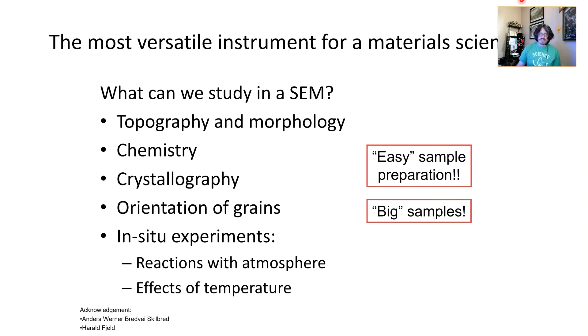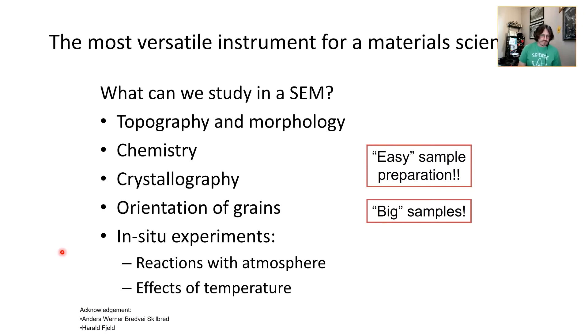The SEM is the most versatile instrument for a material scientist. What can we study in an SEM? Topography, morphology, chemistry, crystallography, orientation of grains — depending on what instrumentation you have. You can perform in situ experiments, reactions with an atmosphere by bleeding gases into the instrument, and observe effects of temperature. Sample preparation is fairly easy — sometimes you just coat with a conductor like gold or carbon. You can put in relatively large samples.